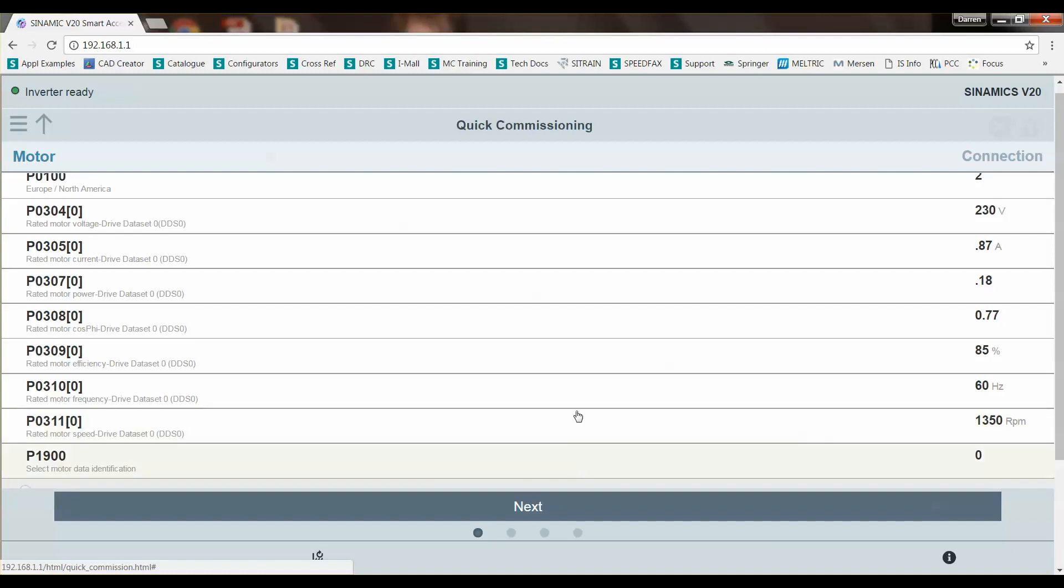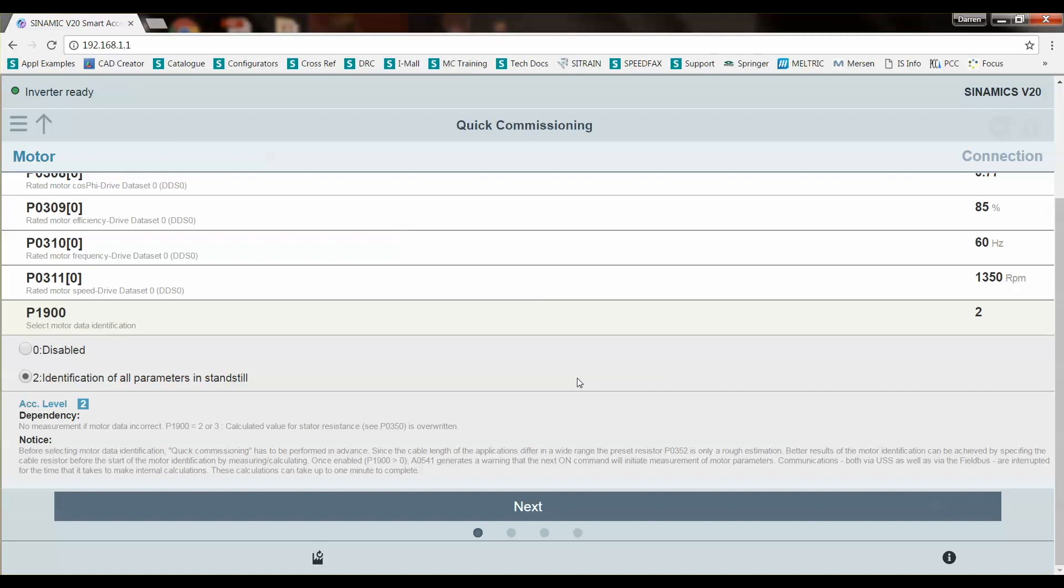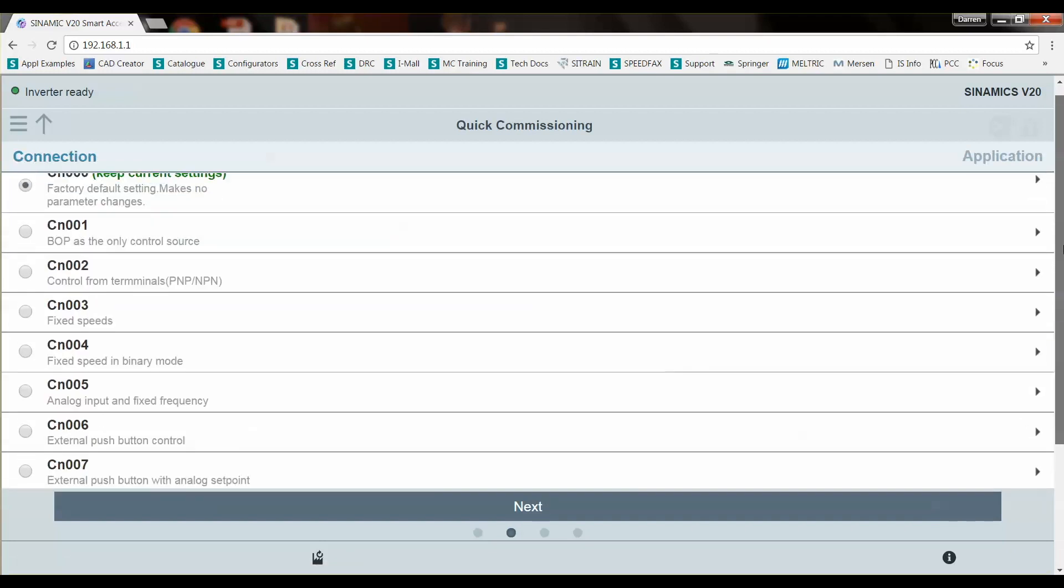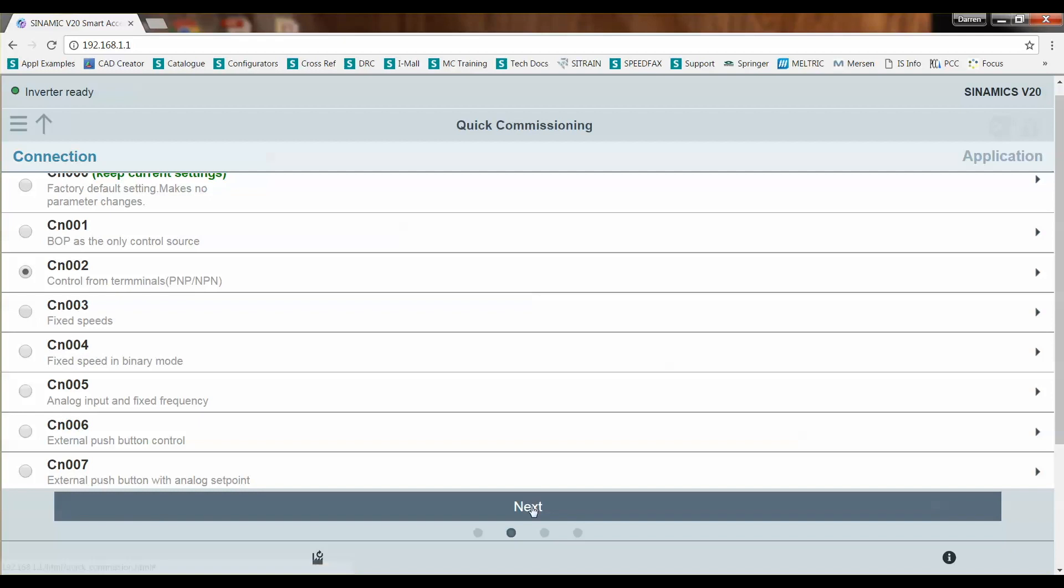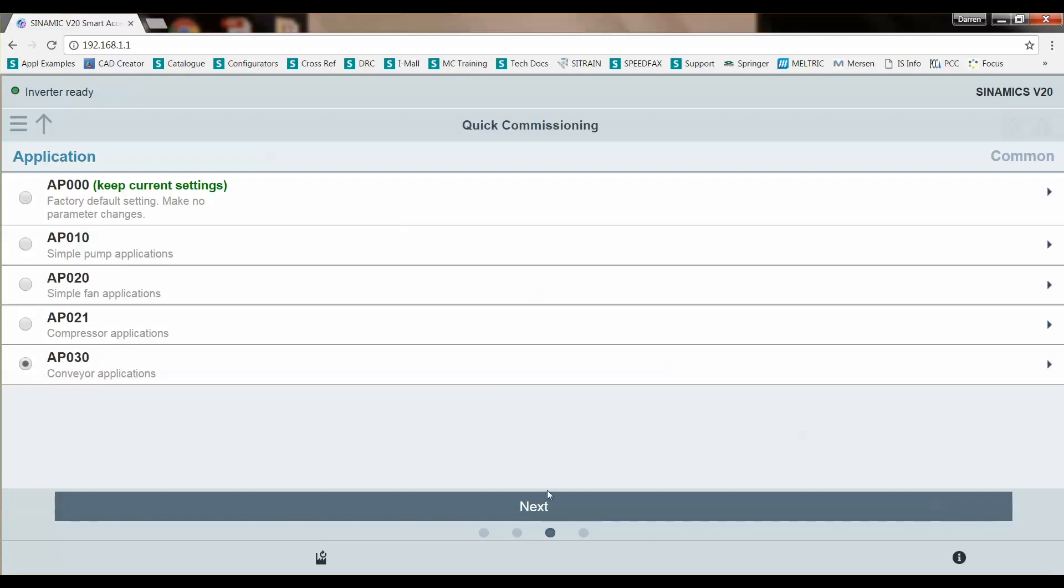And we're going to choose to do an identification of all the parameters, the motor parameters at a standstill. So that's going to make us be able to determine the stator and rotor resistances through this routine. So then we'll click next. This is the connection macro, so how we're going to control the drive. We're doing it through input terminals. Next, we're going to do an application macro. So the application macro is a conveyor application.